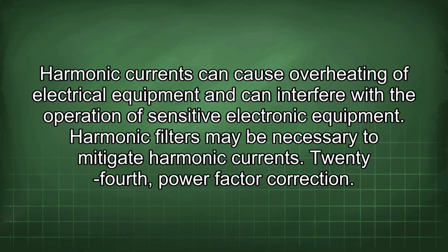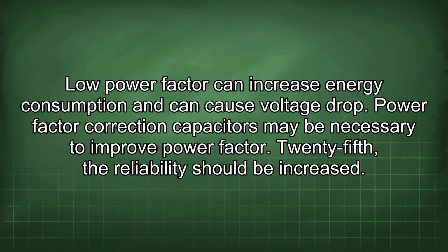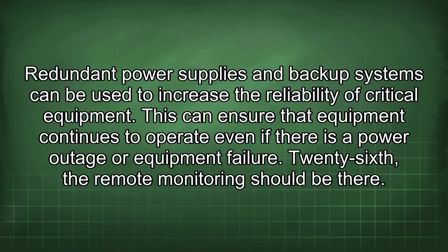24th, power factor correction. Low power factor can increase energy consumption and can cause voltage drop. Power factor correction capacitors may be necessary to improve power factor. 25th, the reliability should be increased. Redundant power supplies and backup systems can be used to increase the reliability of critical equipment. This can ensure that equipment continues to operate even if there is a power outage or equipment failure.